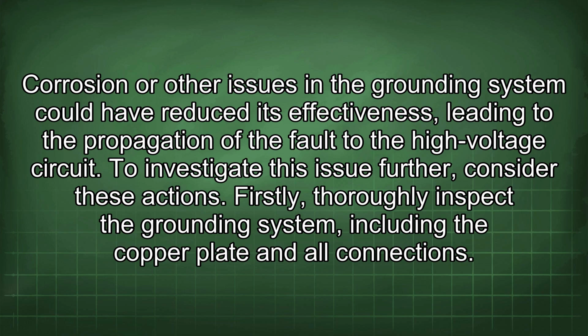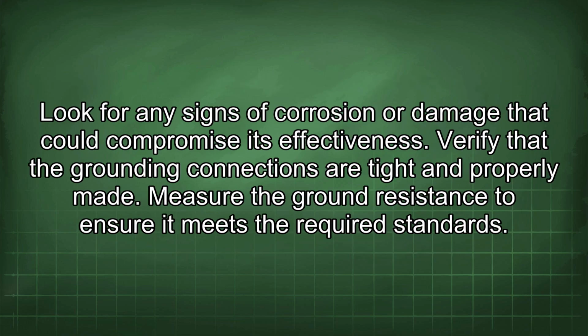Firstly, thoroughly inspect the grounding system, including the copper plate and all connections. Look for any signs of corrosion or damage that could compromise its effectiveness. Verify that the grounding connections are tight and properly made. Measure the ground resistance to ensure it meets the required standards.